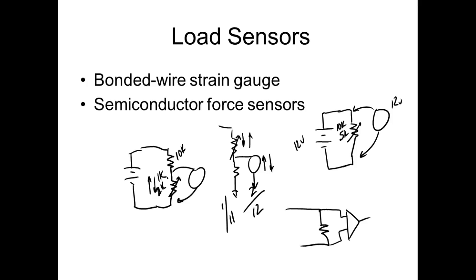So it sounds like one of the load cells was bad to me. Because normally, if you got 3 or 4 load cells and one weigh bridge, it comes in and sums all of them together. But if you got 3 load cells and this one's always giving you a 0, that would give you a problem. So either it was bad, or, well, the load cell sounds like it was bad to me. So it was giving an erroneous reading, and it was still being added in. You can take it out, not make it count, and recalibrate for 3. But then the bridge isn't as sensitive as it would be with 4.